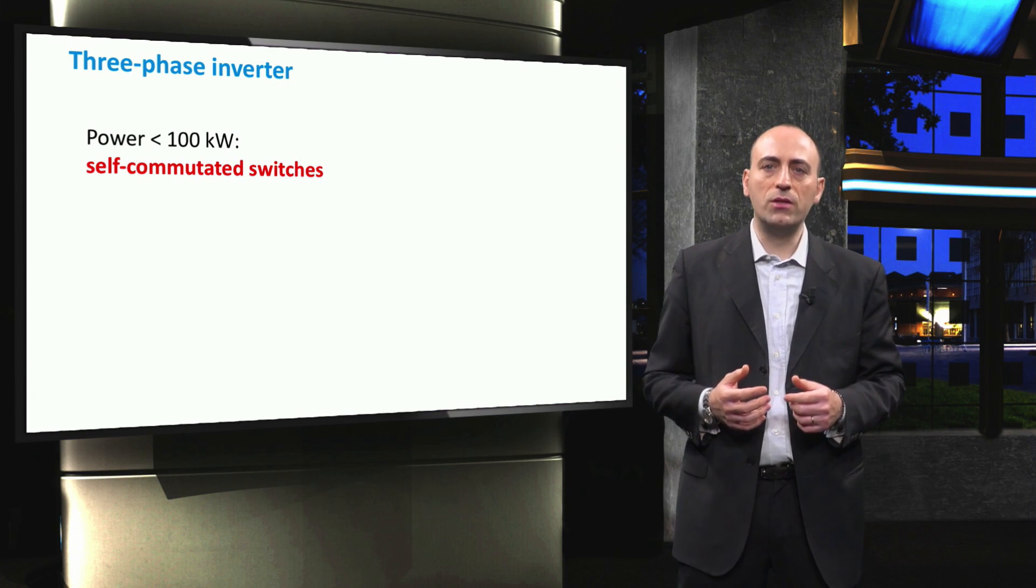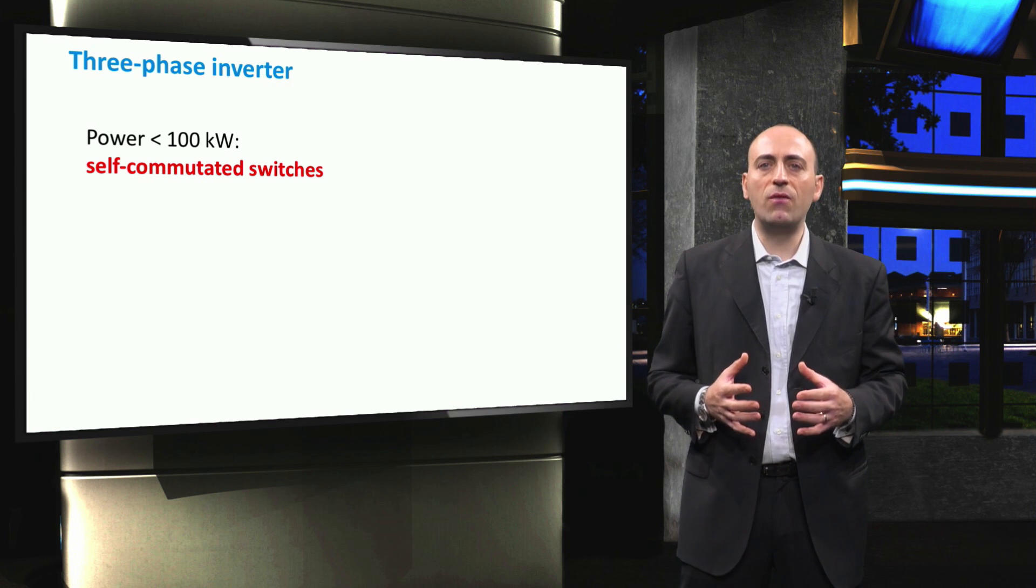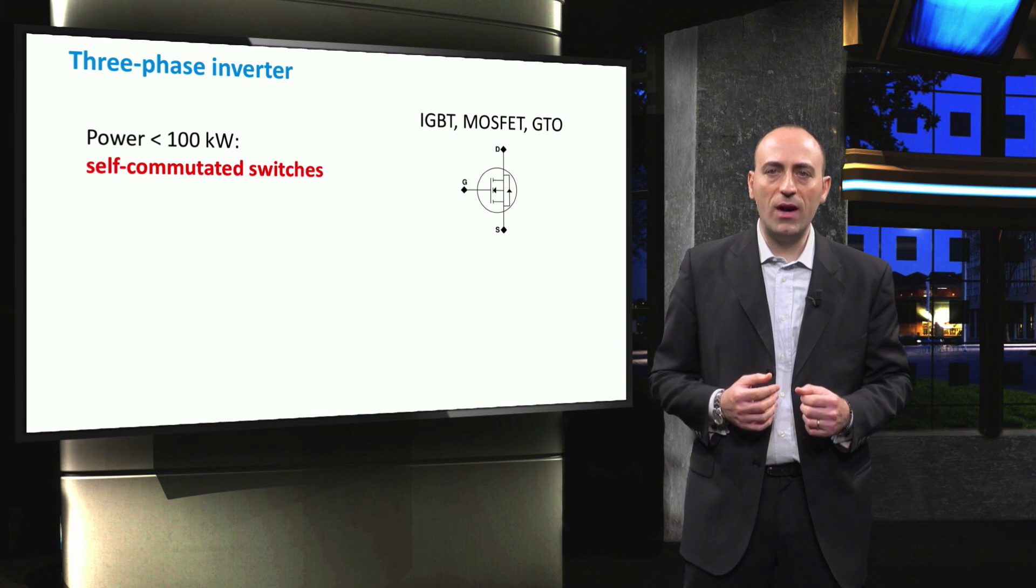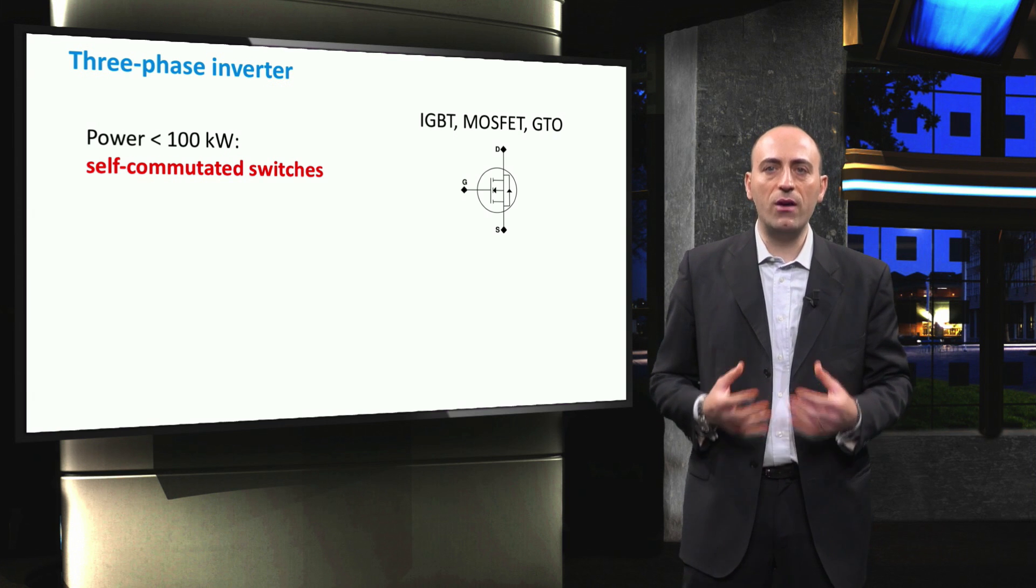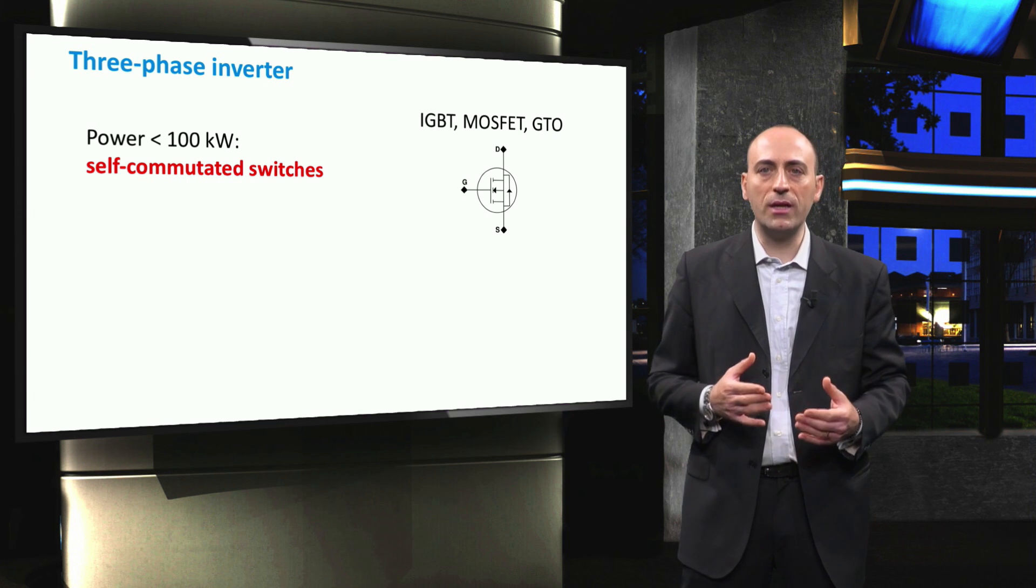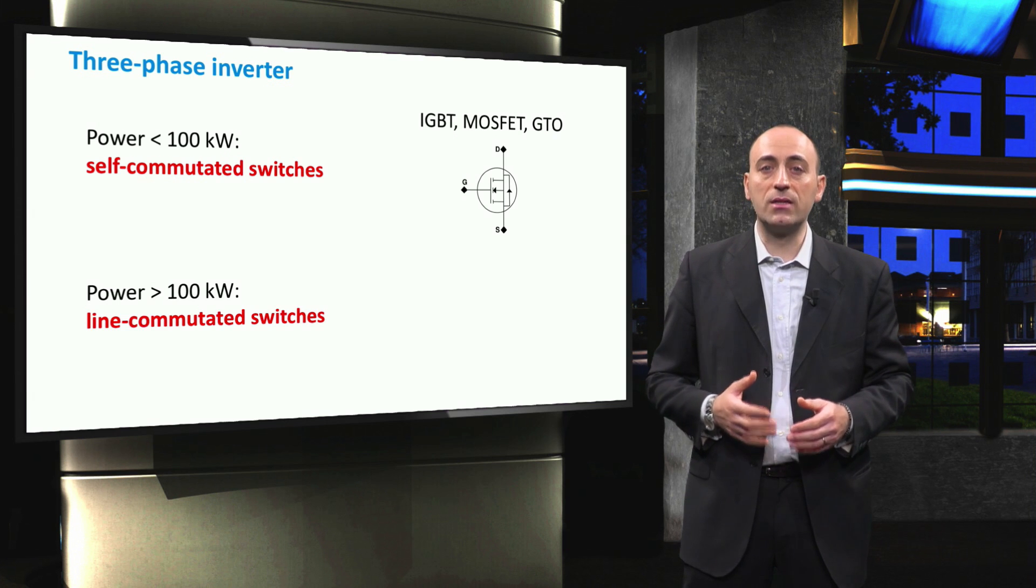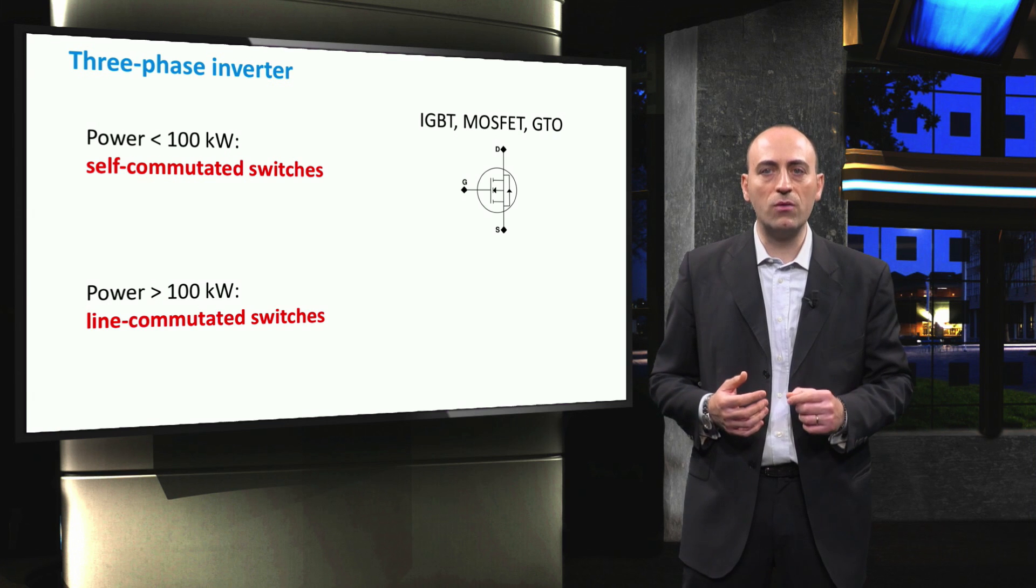If the power converted from DC to AC is less than 100 kW, the switching devices used are usually self-commutated ones. Among these devices we can mention the IGBT, the MOSFET and the GTO. These devices are characterized by very fast switching and feature a controller that takes care of the opening and closing of the transistors. When it comes to power ratings higher than 100 kW, line-commutated semiconductor devices, such as Thyristors, are used.